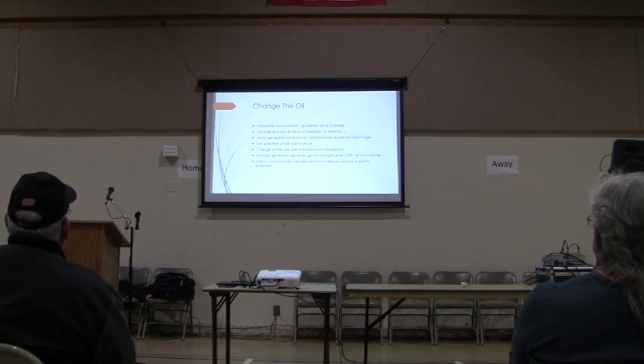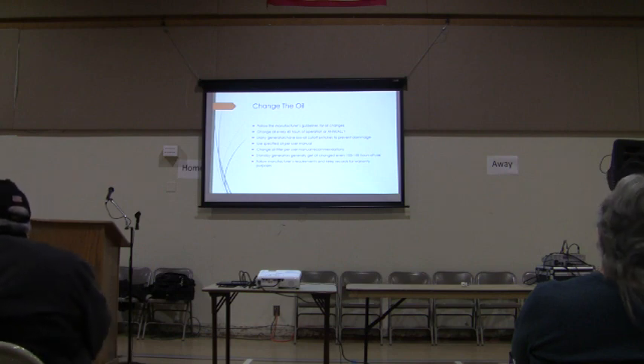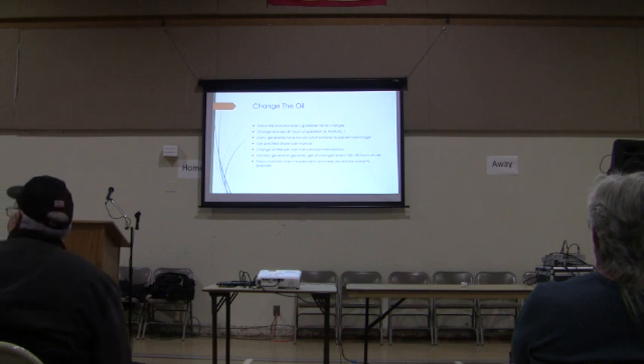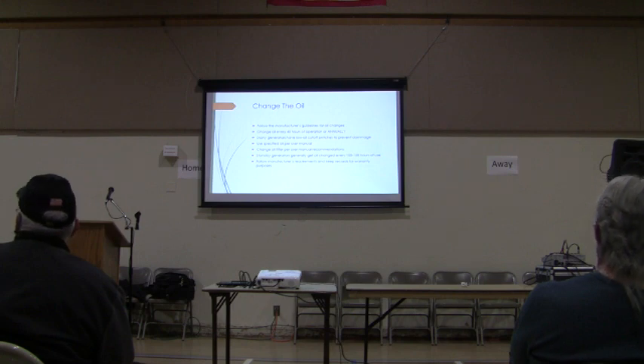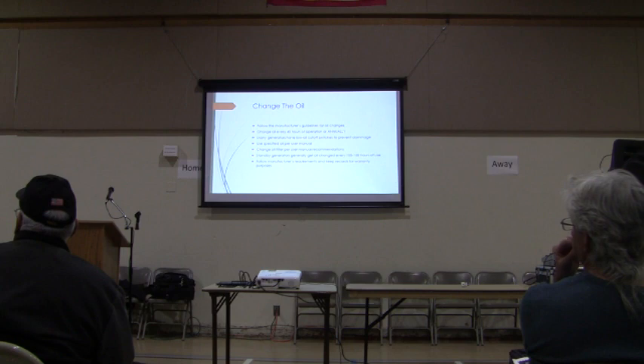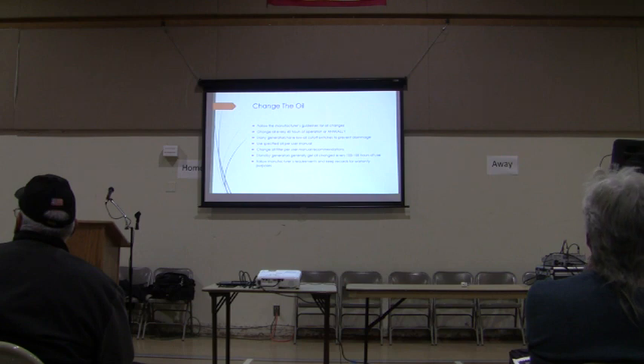Standby generators, typically the oil will get changed every 100 to 150 hours. Don't forget, they ran once a week or once every 2 weeks. So they've got a little more run time, but that also keeps the circulation a little more, and it's going to be synthetic. Follow the manufacturer's requirements and keep records for warranty purposes. Prove that you did the maintenance. Otherwise, it's like you buy a new car, you never go get the oil changed, it never gets put into Carfax, and the engine dies at 35,000 miles. They open it up and there's nothing but tar in the crankcase.